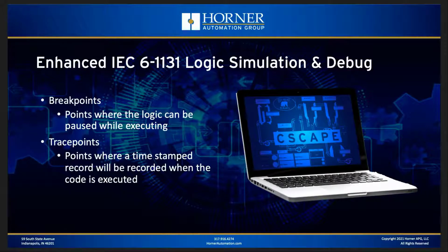I don't think breakpoints are supported in all the languages, but certainly for structured text and for ladder, those are fully supported. And then we also have a feature called trace points. Now trace points are placed in the logic as well, but those don't cause the logic to be paused. They actually cause a timestamp to be created every time that logic is executed. So that can provide solid evidence that yes, that logic did actually execute, even though you don't pause in the middle there like you would with a breakpoint.